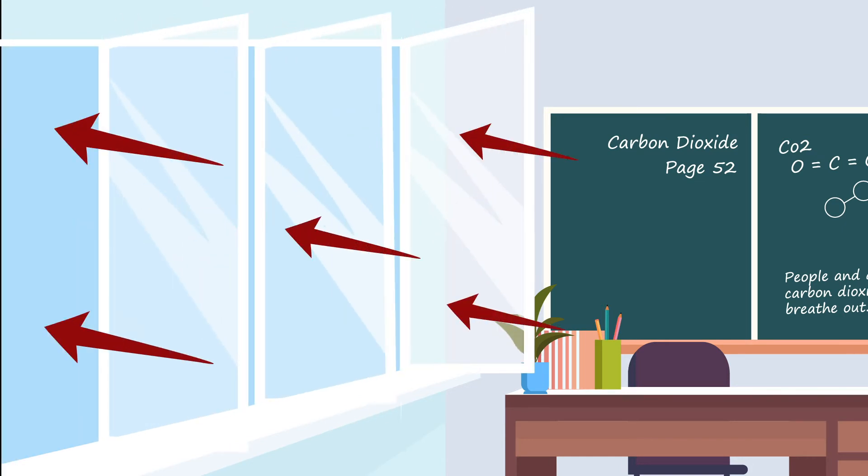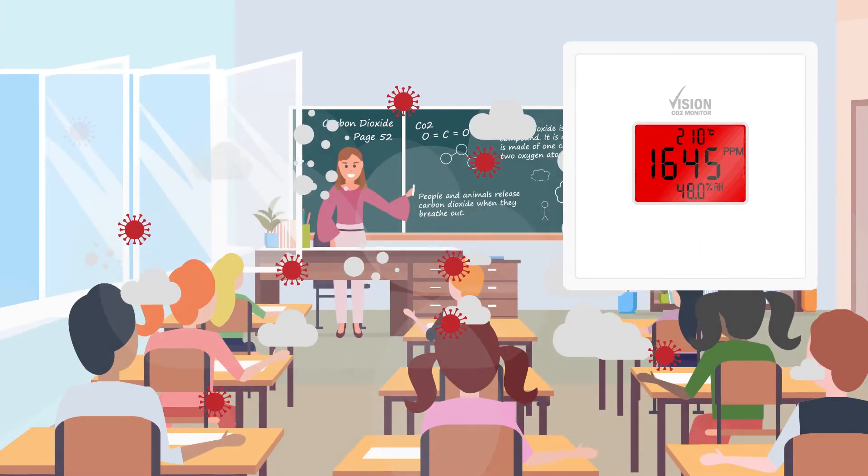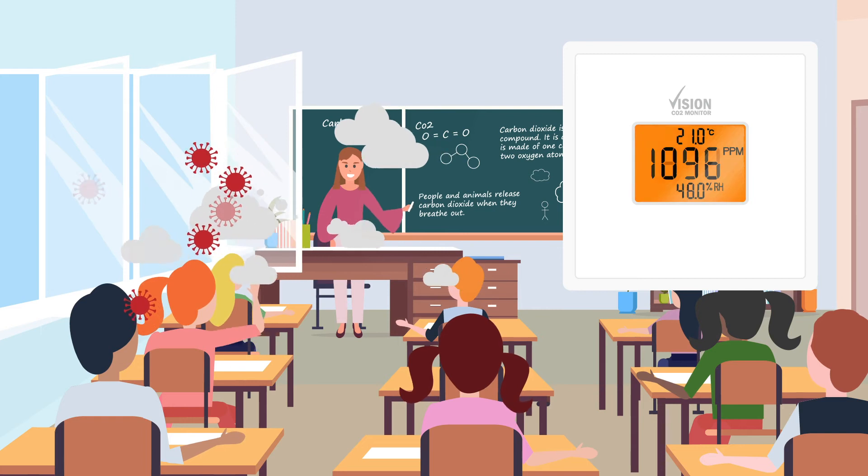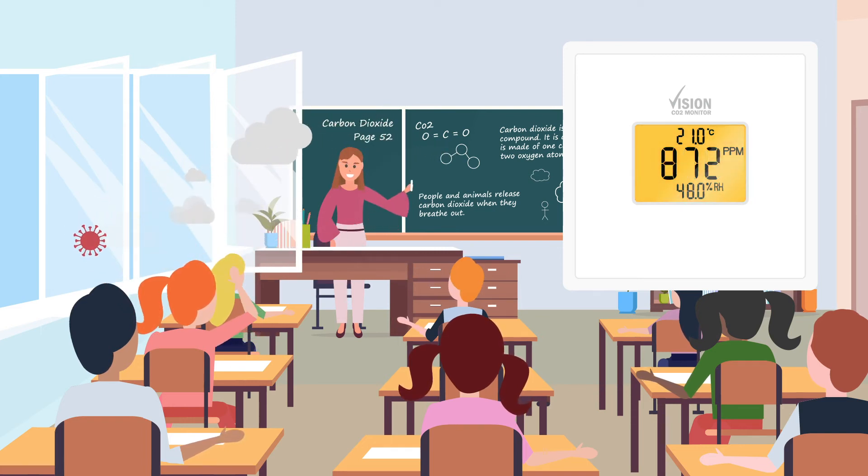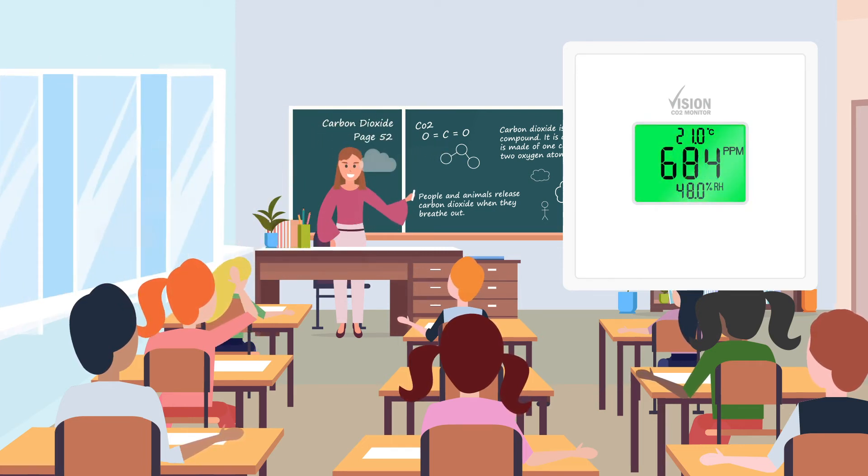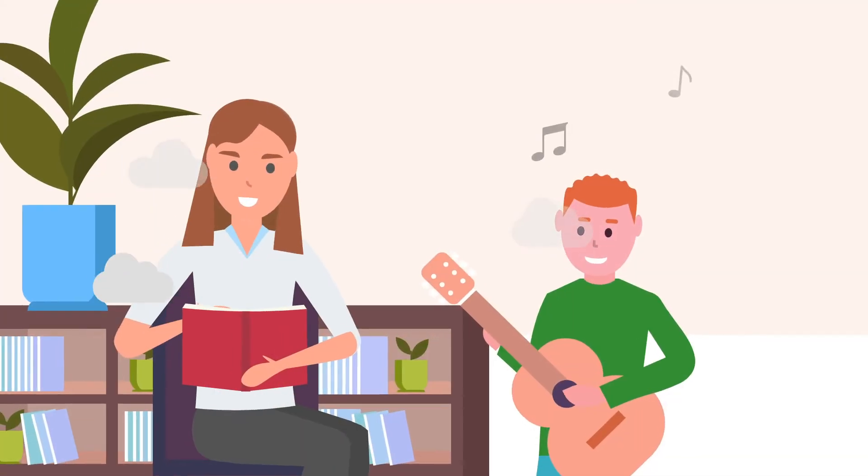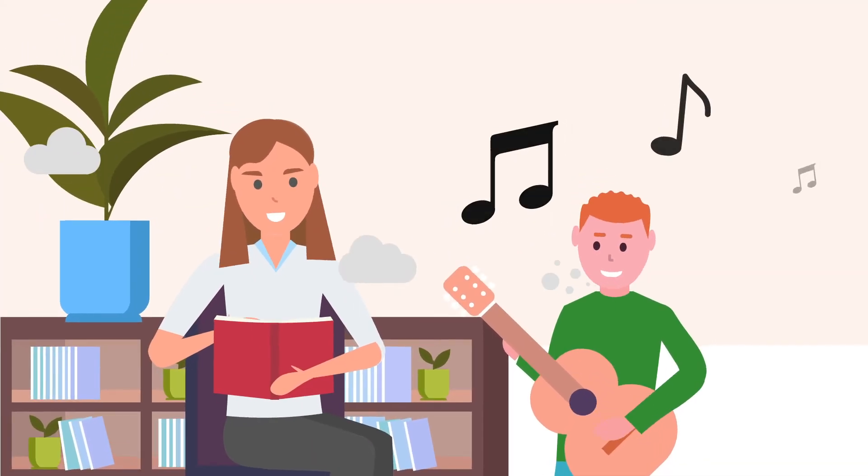If high CO2 levels are present, it is recommended that the room is purged by increasing ventilation as much as possible until the levels are reduced. The ventilation can then be decreased, providing a low CO2 level can be maintained.